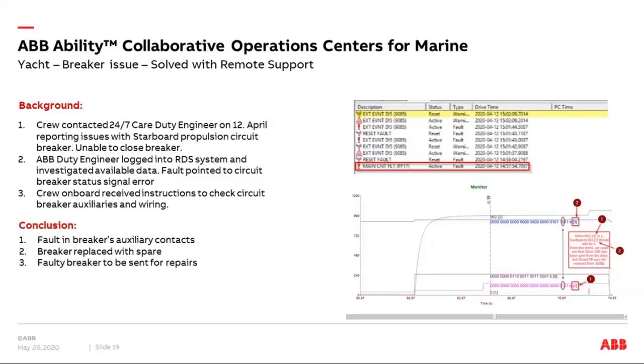We connected to the vessel via remote link and analyzed the available data. The fault immediately pointed towards the circuit breaker auxiliary signals, the status signals going between the frequency converter and the breaker itself. Again, detailed instructions were given via chat functionality to the crew on board, and they were able to detect a faulty coil on the breaker or auxiliary contact.